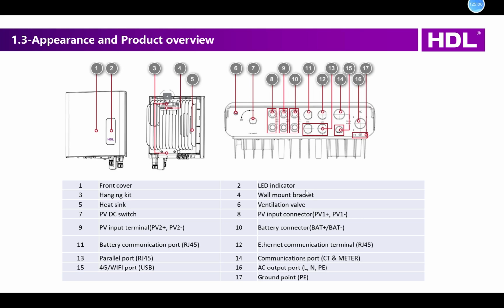You have PV input ports, and there are 2 of them because this inverter supports 2 solar arrays - it has 2 MPPT ports. You also have battery connectors, and the battery needs to communicate with the inverter to be commanded for charge and discharge.